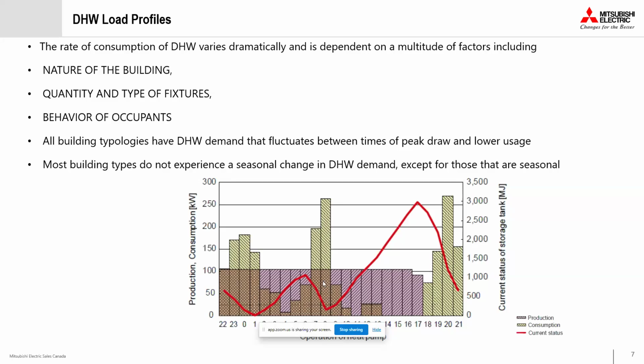So all building typologies have domestic hot water demands that fluctuate between times of peak draw and lower demand. You have a peak draw maybe in the morning and evening when all the people are inside, or you are taking a bath, or you're coming from work. So you have a peak time, and in between there is a time of low demand, and the system can reproduce or store the water. Most building types do not experience seasonal change, so we will have continuous or similar demand all around the year, except where you have a seasonal building, maybe a resort or something. There, in the summer or winter you have more occupancy, and because of that your demand will change.